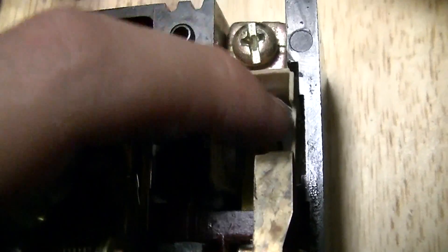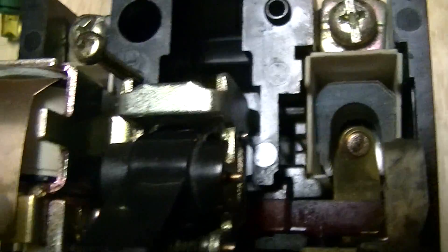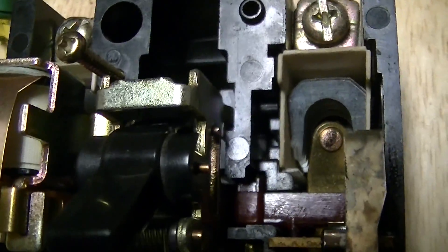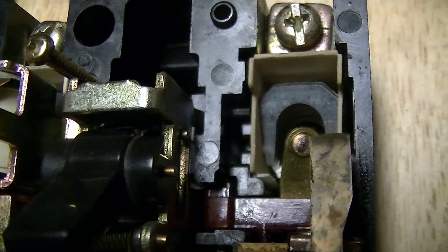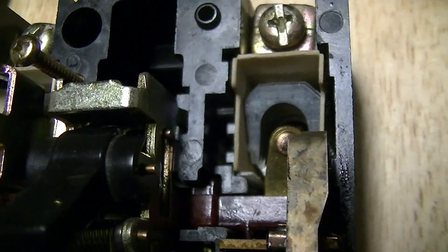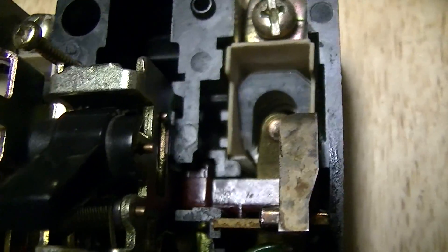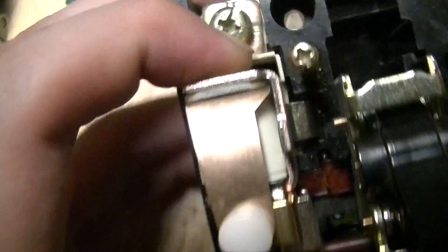But anyways, the arc bows upward, touching these series of metal plates which are all electrically insulated from each other. What that does is the metal plates absorb heat from the arc, thus cooling it to the point where the air is no longer electrically conductive, thus quenching it. There's also the same arrangement with that contact set, except that's obscured by the solenoid.